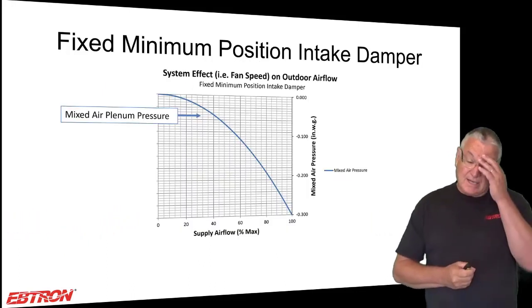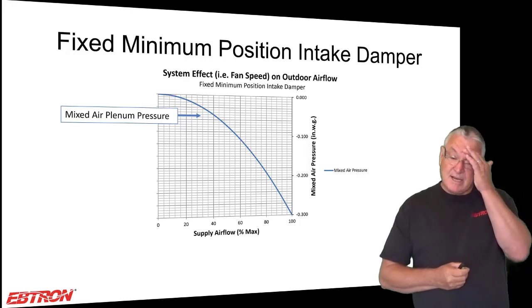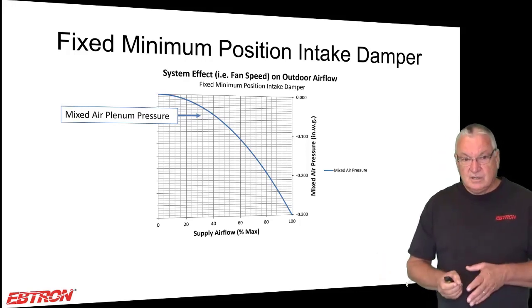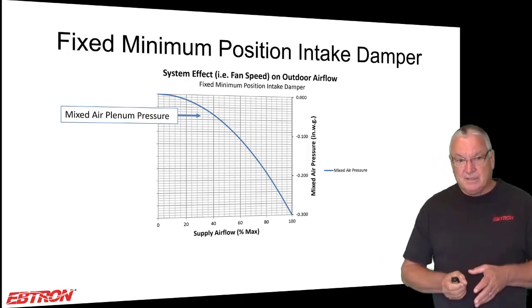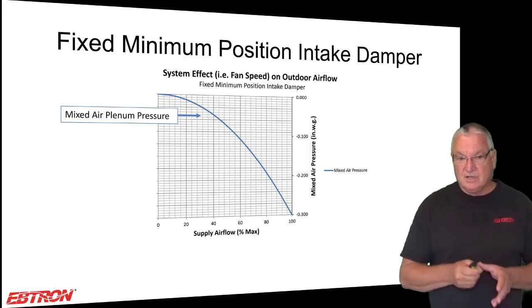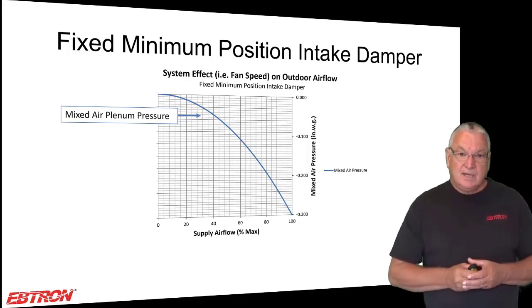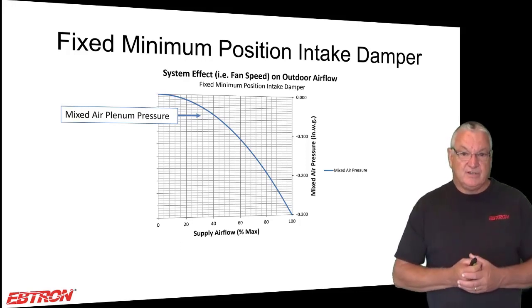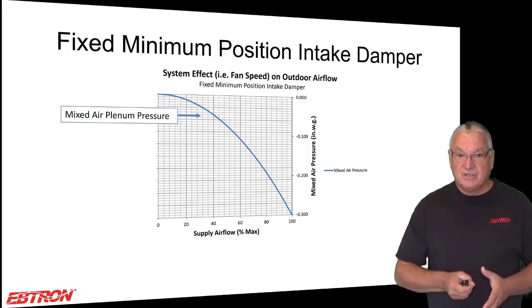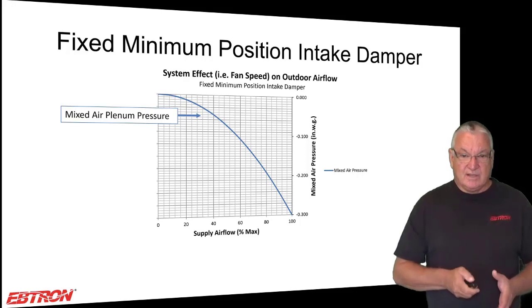And so I like to look at a simple example where we look at the combined louver damper pressure drop at design flow, design supply flow, and design outdoor airflow. We're going to say that there's a 3/10 of an inch drop across it. So the mixing box had to be negative 3/10 of an inch to bring in the outdoor air that we wanted.